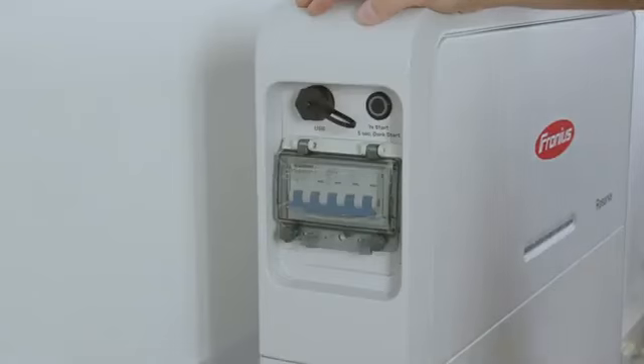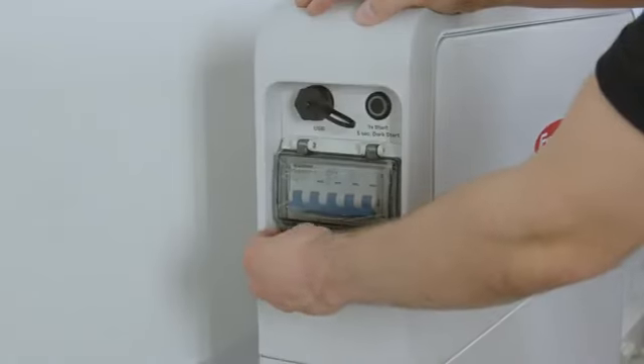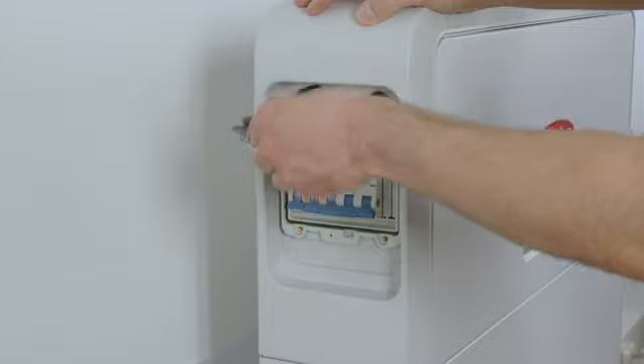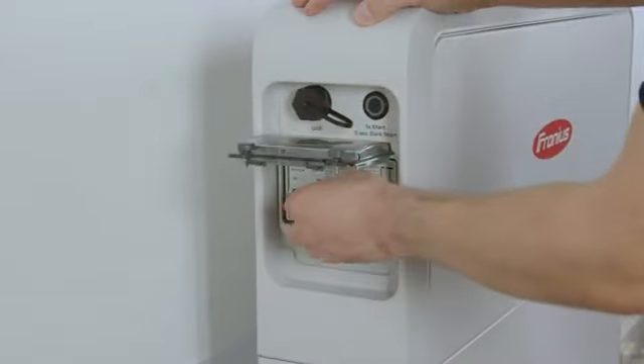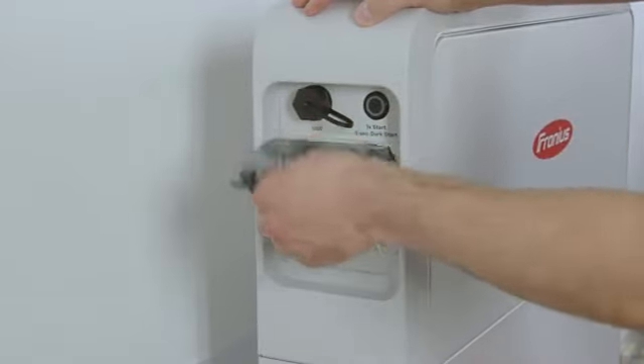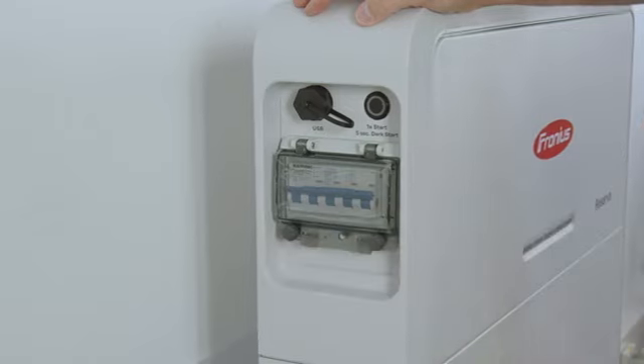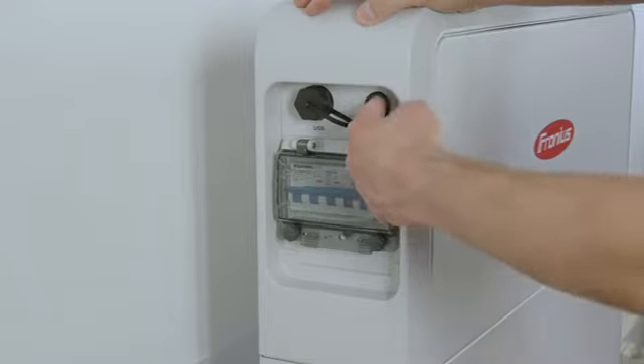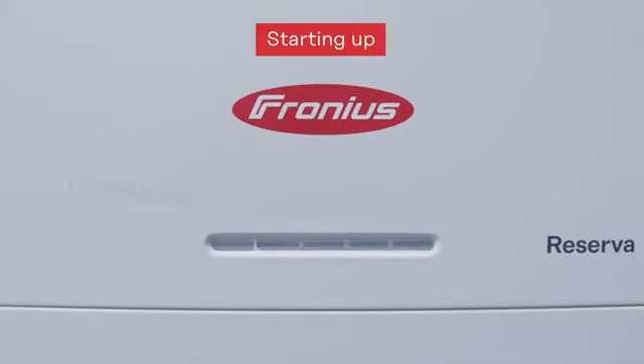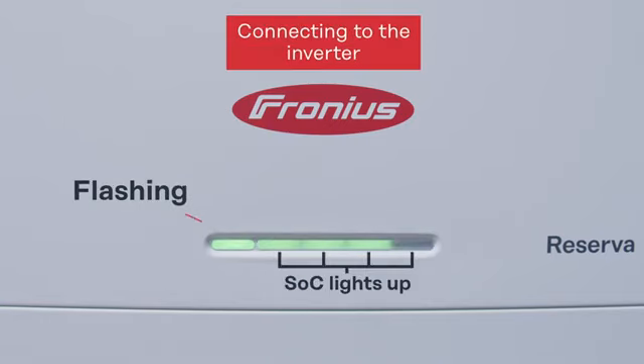To activate the battery, please open up the cover of the main switch with the two screws here, open up the cover and then activate the main switch on the battery. After that, close the battery cover again and press the start button once to activate the battery system. The battery will then drive up and start itself, and you can see that by the flashing status LED on the left side.